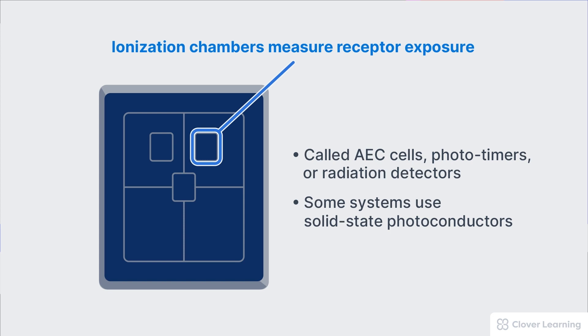The ionization chamber is a very important part of the AEC system. Most systems have three small chambers rather than one large chamber. Sometimes these chambers are called AEC cells, and depending on the part being imaged, you can choose to activate one, two, or all three of the chambers. Some systems have more than three, but they work in exactly the same way. AEC cells are also sometimes called phototimers or simply radiation detectors. Some AEC systems use solid-state photoconductors rather than ionization chambers, but they accomplish the same thing.